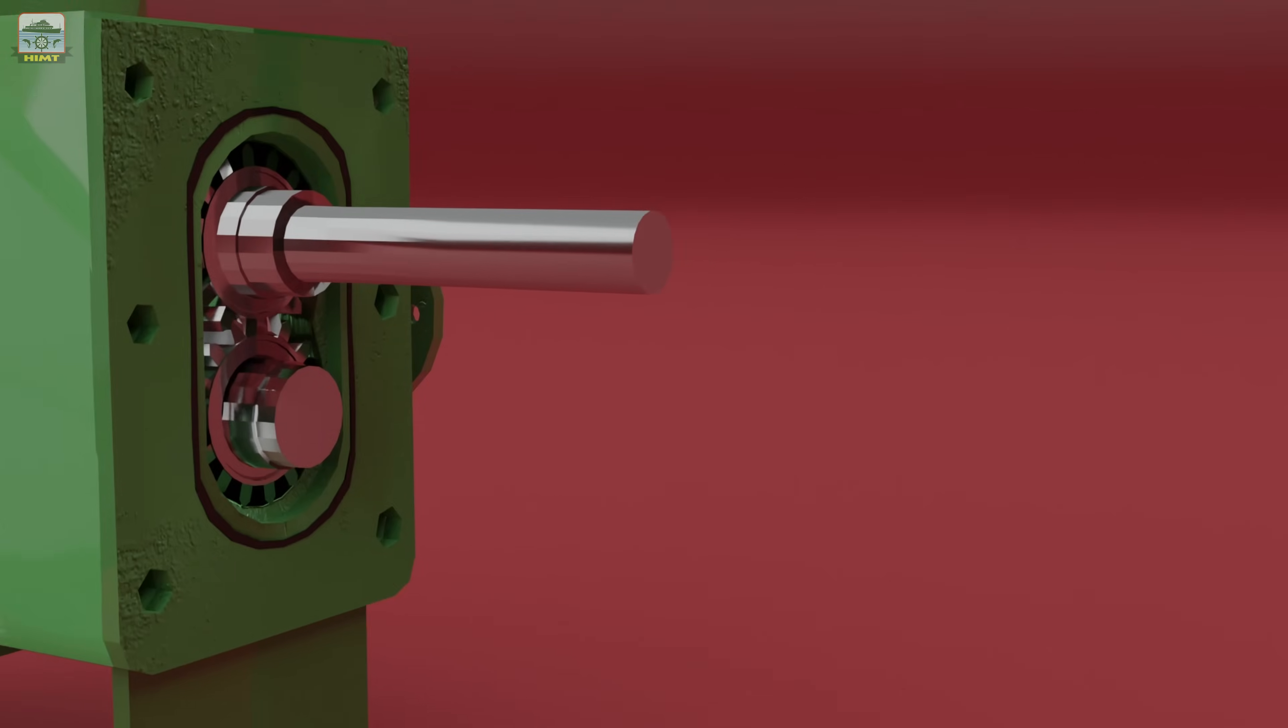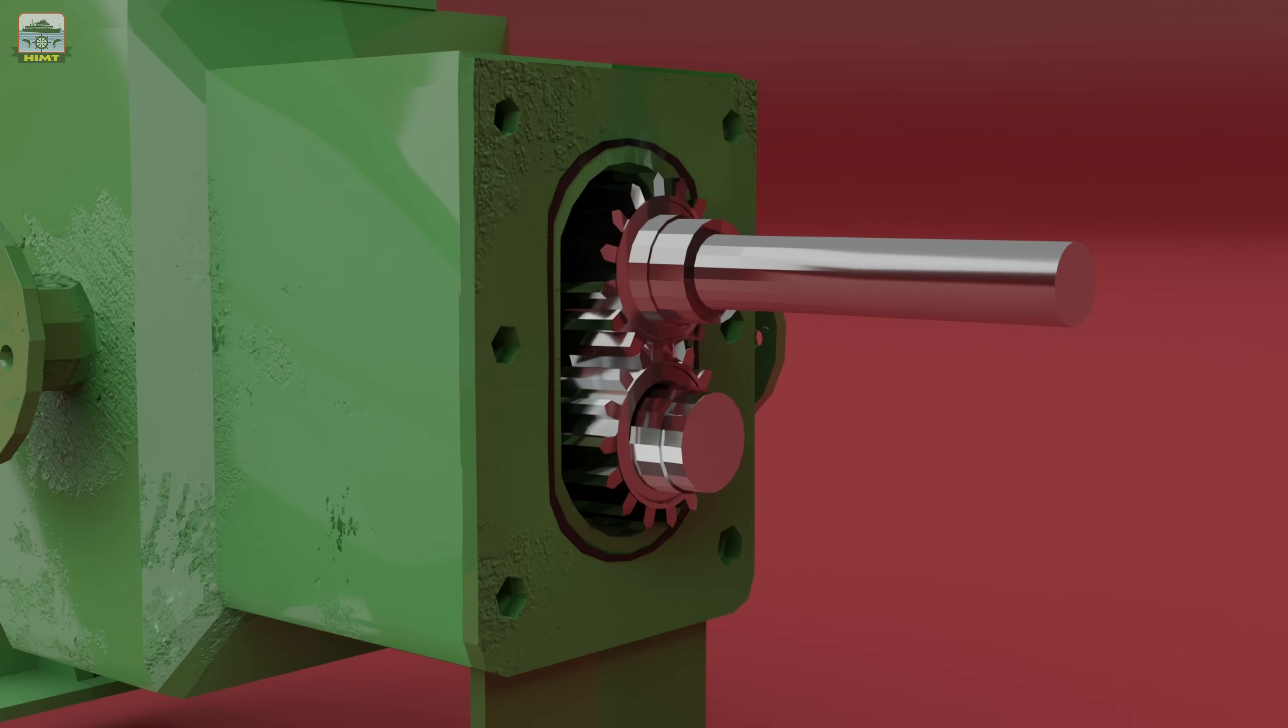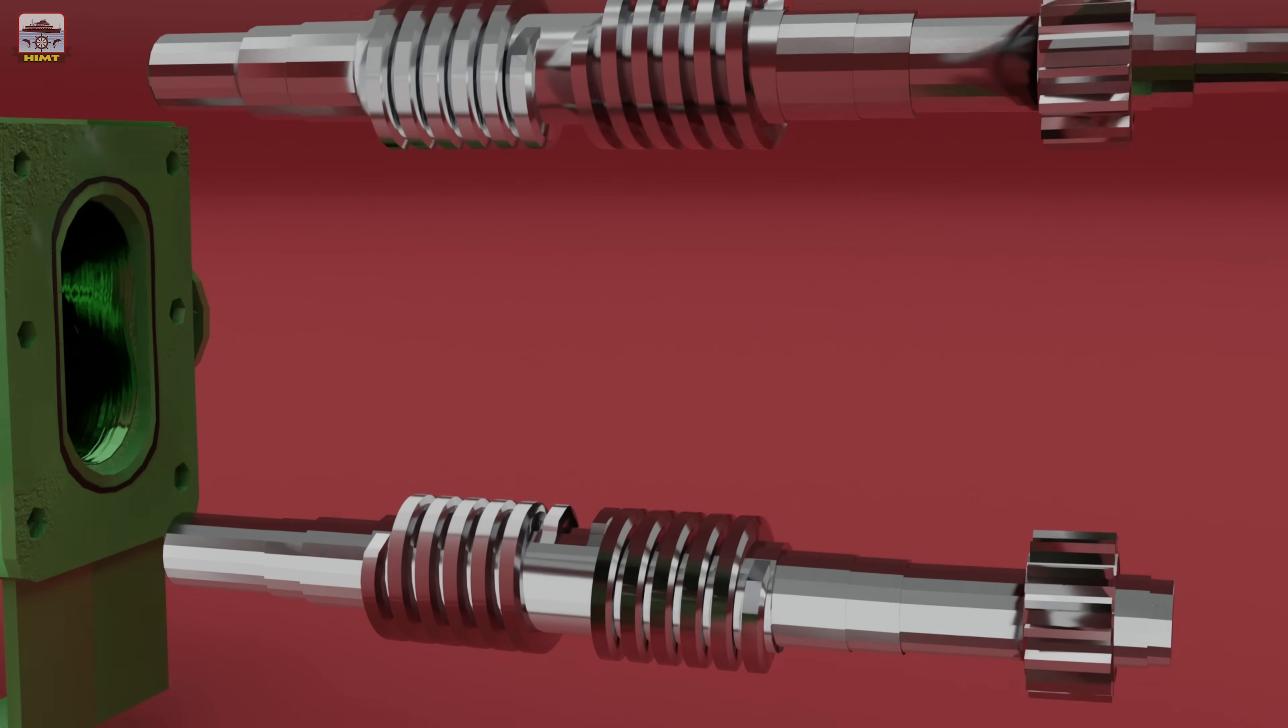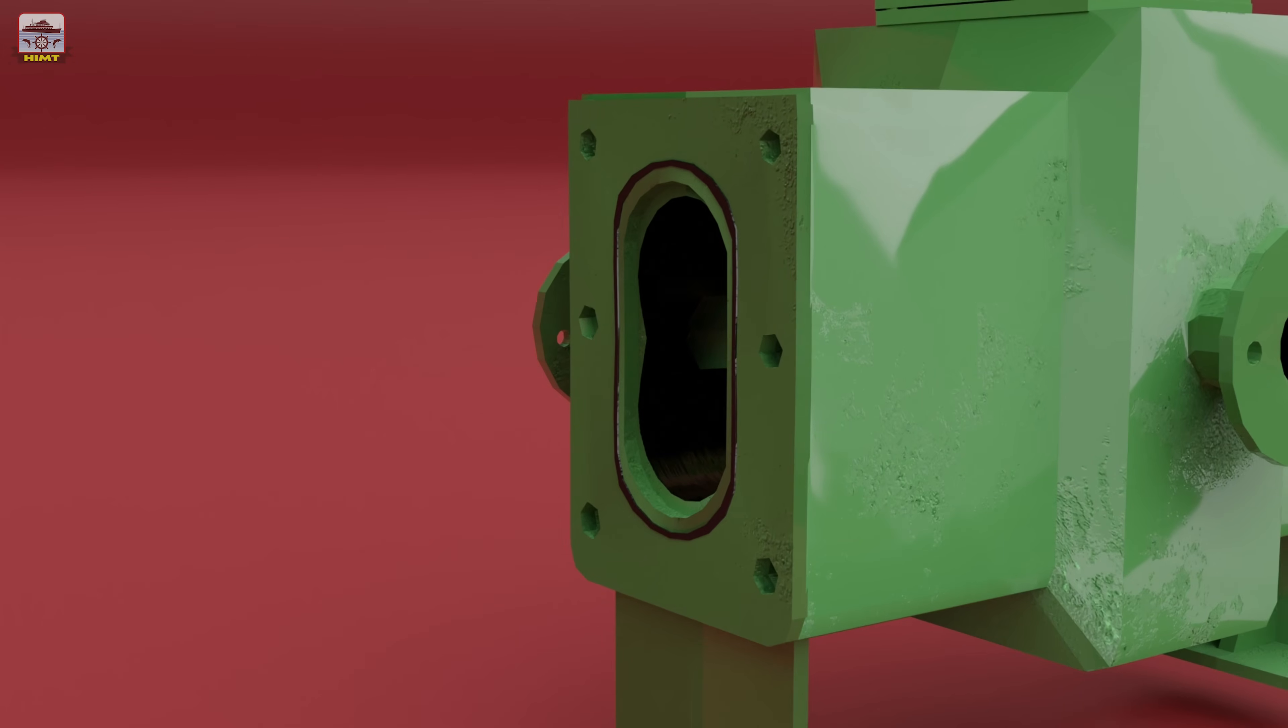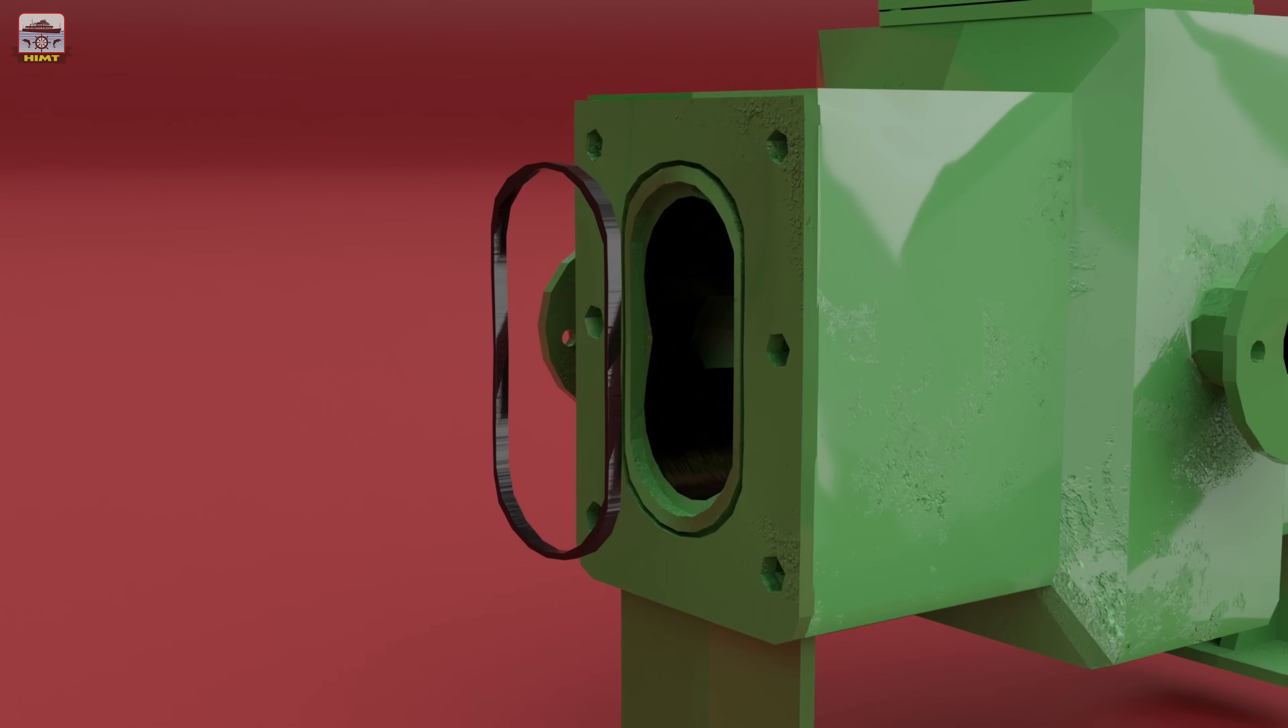With the covers removed, carefully extract the drive shaft and the driven shaft from the pump body. Now, let's remove the sealing rings. Begin by taking out the sealing ring in the drive end of the body, followed by the sealing ring in the free end of the body.